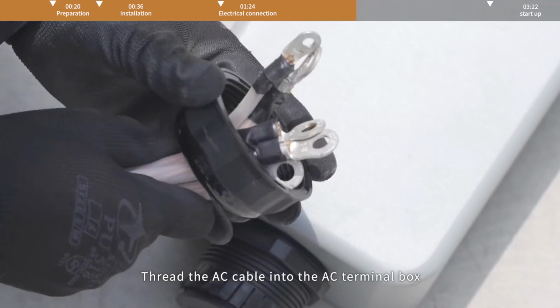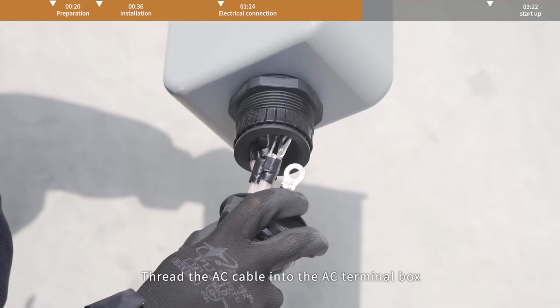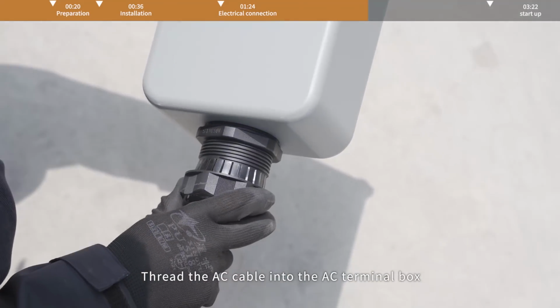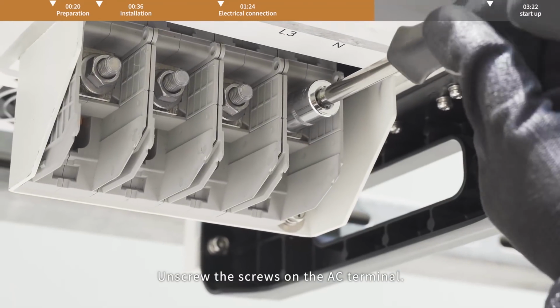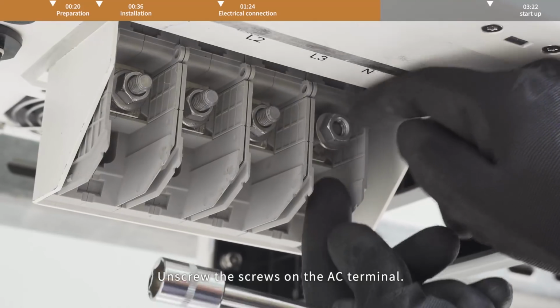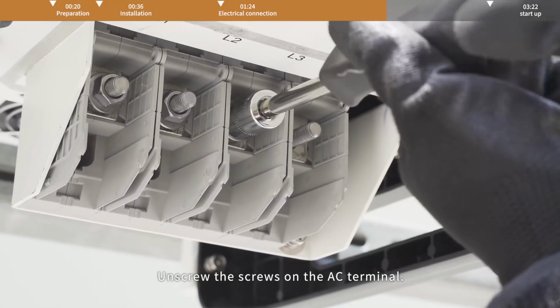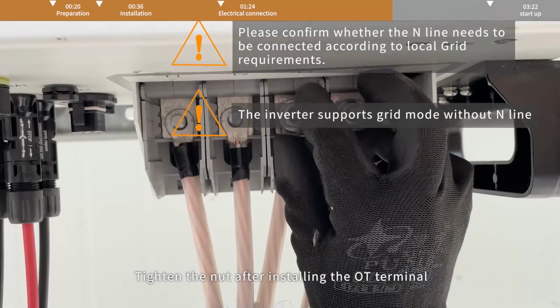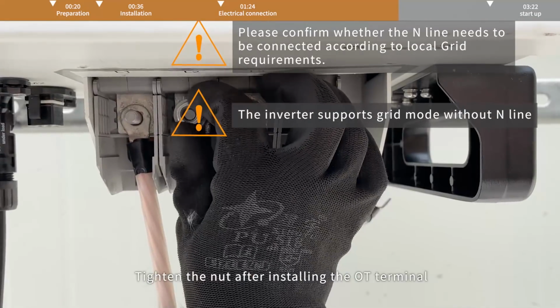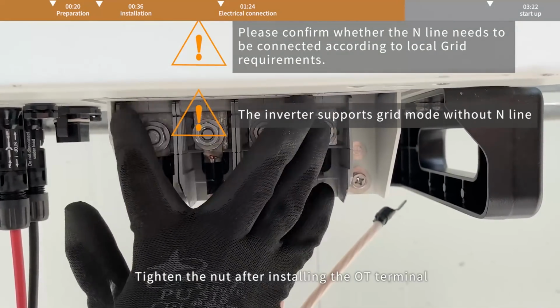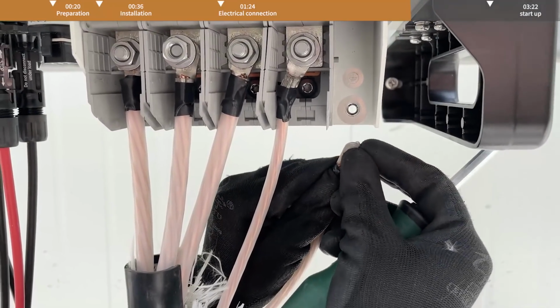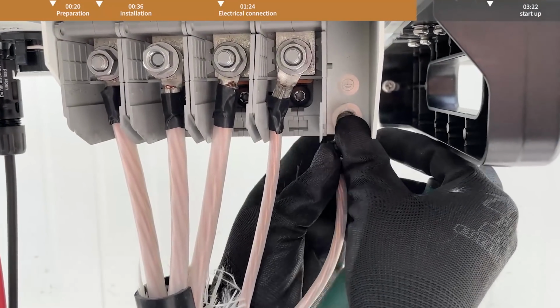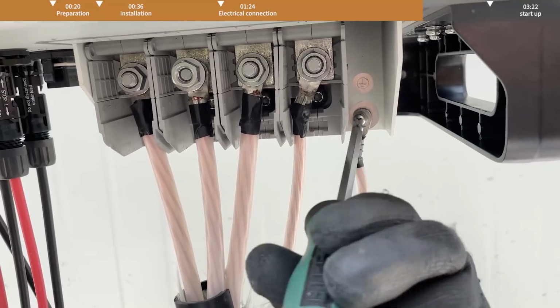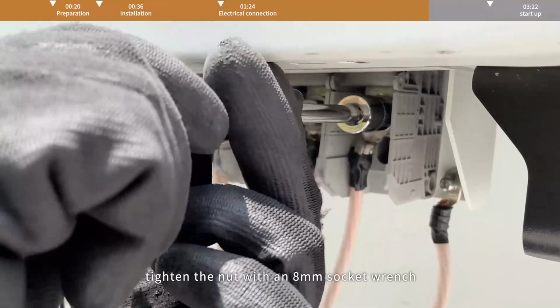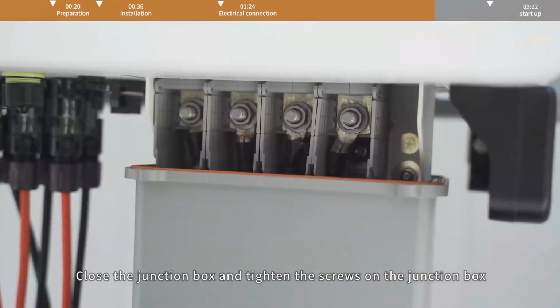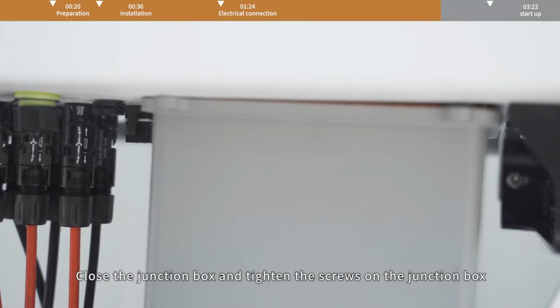Thread the AC cable into the AC terminal box. Unscrew the screws on the AC terminal. Tighten the nut after installing the OT terminal. Tighten the nut with an 8mm socket wrench. Close the junction box and tighten the screws on the junction box.